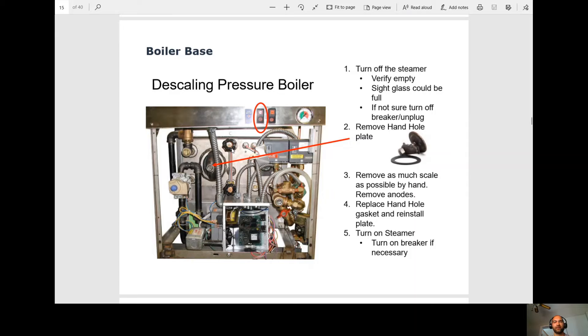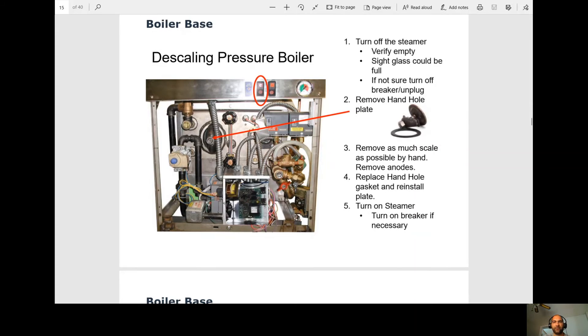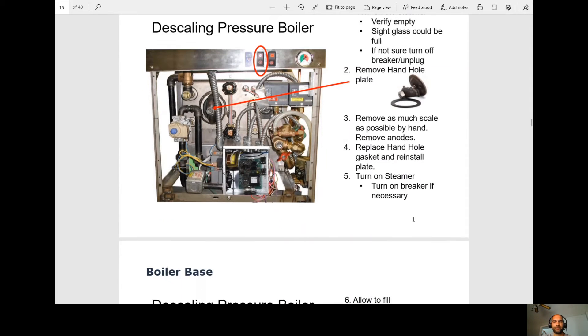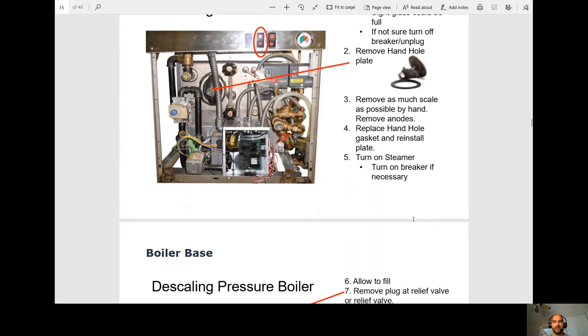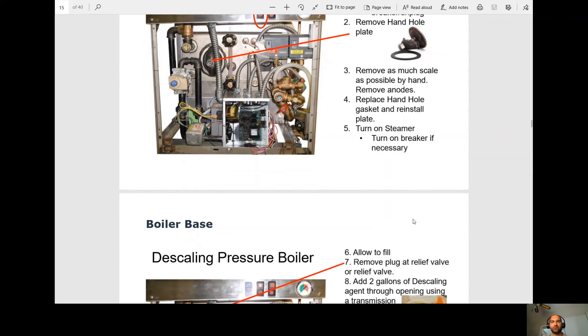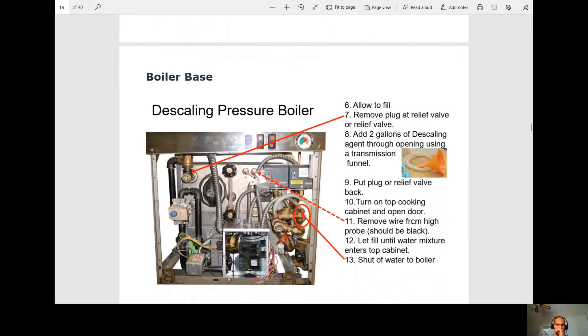So you want to do your blowdown and then at that point, you would come and remove this handhole plate. At that point, you remove as much scale as possible by hand, so you just put your hand and arm in there. Take as much as you can. You want to remove the anodes. You want to put back the handhole and change the gasket if needed. At that point, we're going to turn on the steamer. So you're going to let the steamer fill.